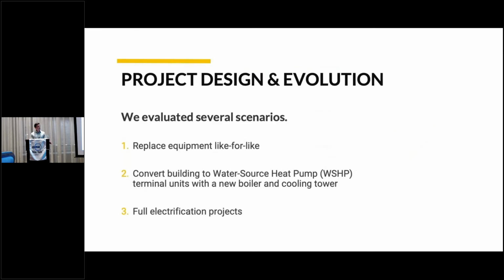With these four things combined, we started looking at several different scenarios. We started with a like-for-like equipment replacement, but quickly ruled this out because there's no way a like-for-like replacement addresses Local Law 97. So we shifted our attention to converting the building into a water source heat pump system with new terminal units, new boilers, and a replaced cooling tower. We were doing the asset renewal, but changing the system a little bit.